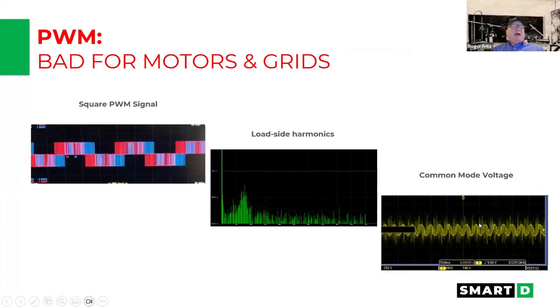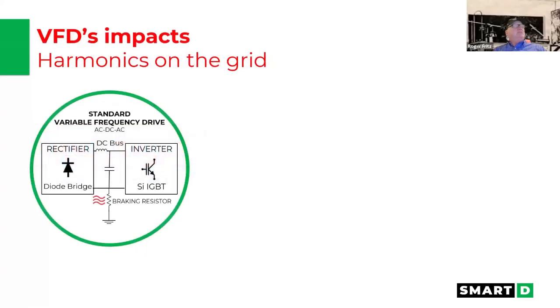And then what happens is because of all of these harmonics, you get imbalances. And so you get what they call common mode voltages fed to the motor. And that's where those spikes come from that you'll see. And that's why in the 80s and 90s, everybody went to special insulation in the motors. And now they're coming out with special motors. So again, you get the harmonics fed back to the grid because you have a diode front end.